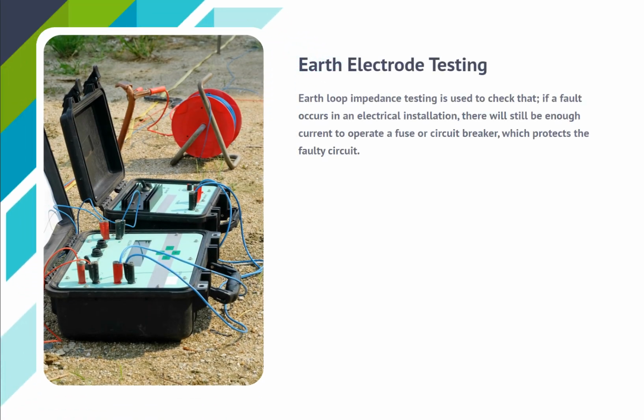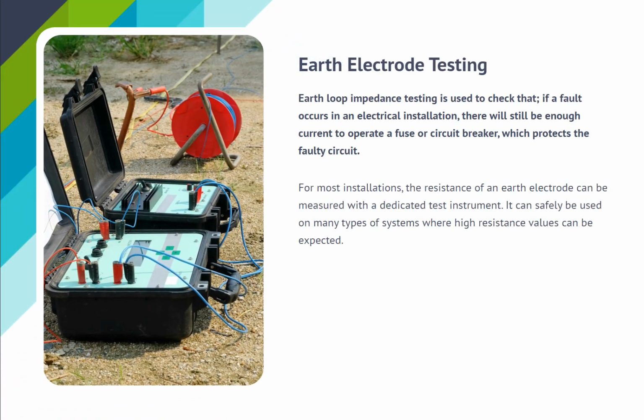Earth electrode testing. Earth loop impedance testing is used to check that, if a fault occurs in an electrical installation, there will still be enough current to operate a fuse or circuit breaker, which protects the faulty circuit. For most installations, the resistance of an earth electrode can be measured with a dedicated test instrument. It can safely be used on many types of systems where high resistance values can be expected.